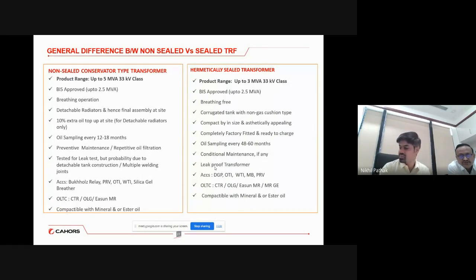I will add one more thing. In non-sealed conventional transformers, where we provide the silica gel breather, we have to be very alert to check during preventive maintenance whether that silica gel becomes pink. If it is pink, and if somebody has not observed that, then moisture can enter inside the transformer during breathing, during the operation of the transformer, which will lead to a drop in the BDV level of the oil and subsequent damage to the transformer. It can happen. That's why we have to be very alert to check this during preventive maintenance of all other parts in non-sealed transformers.